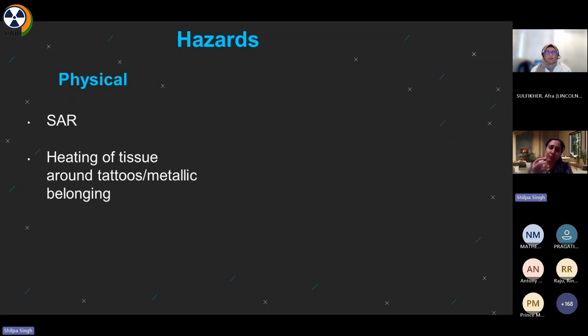So if there is any particular organ and the heat goes above 1 watt per kilogram of body weight, the MRI scanner is smart enough to detect that, and it will pause the scan immediately until the patient's tissue has cooled down below the safe levels. We cannot proceed with the scan. So we need not worry much about the SAR. But yes, there are certain limits that we should follow for the maximum SAR given to the body, head, or per kilogram of body weight. Heating of tissue around the tattoos and metallic belongings, similar to what we have seen with the gradient coils.